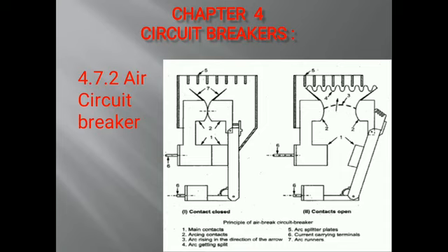While separating, the main contacts are separated first and the current is then shifted to arcing contact. Later on, the arcing contact will also start separating and arc between them is forced upward by electromagnetic forces and thermal action.